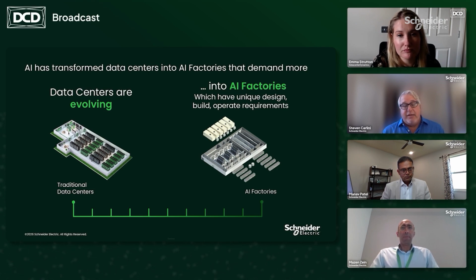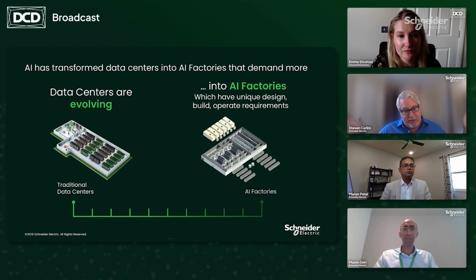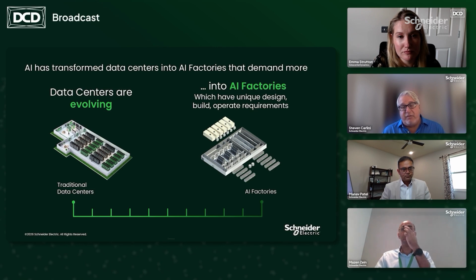You could see there's going to be many more servers than in the traditional setup, where you used to have viewing areas and balconies to look over rows and rows of servers. Now the IT section of the data center is going to be very small and very, very power dense. So you have little room for the IT space, but a lot more room for power systems like generators, switch gear, UPS systems, and transformers - a lot more equipment outside the white space, while the white space itself becomes very densified.